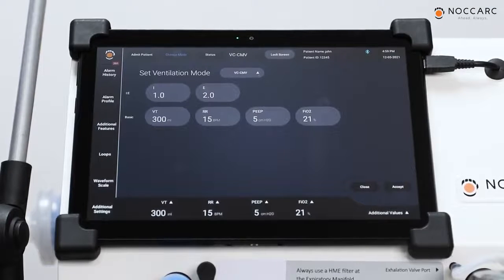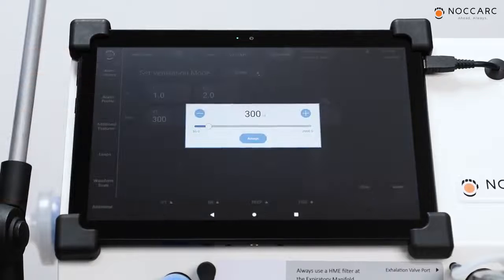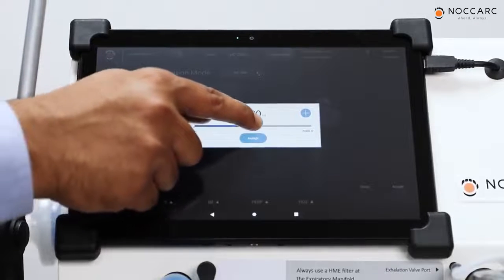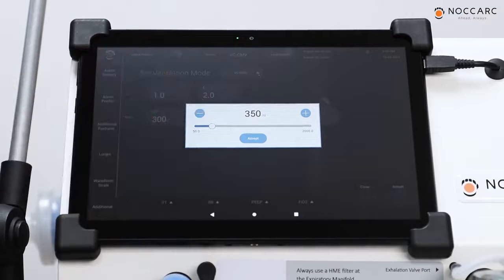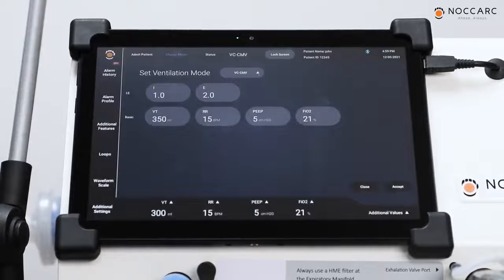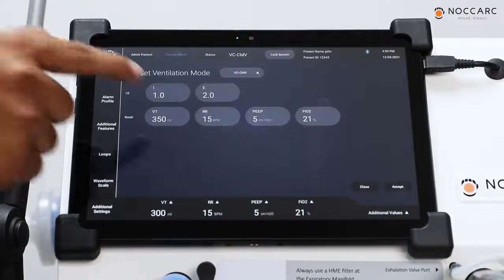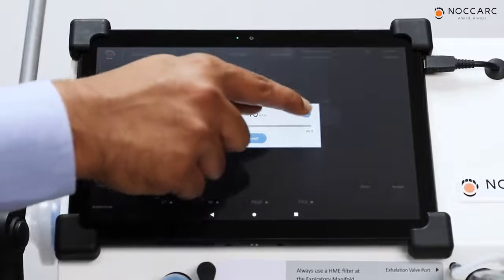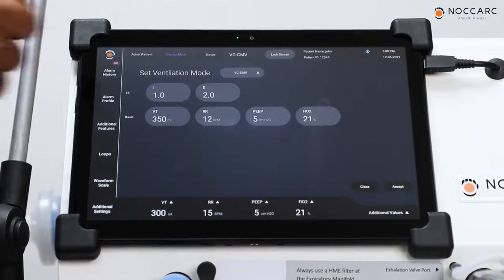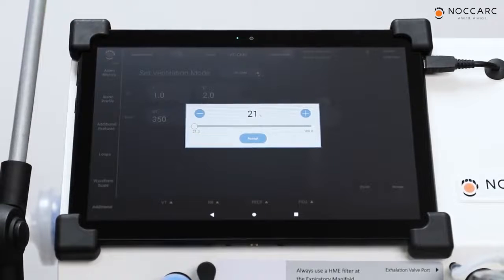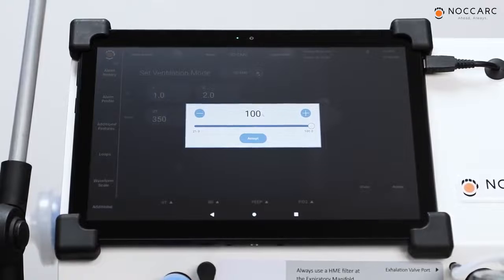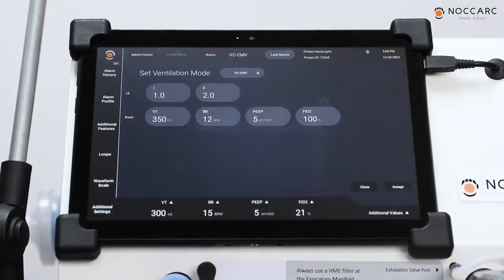To change any parameter, press on that particular parameter. Let's say I want to change the tidal volume. I will press on this VT. Now you can change the parameter by using this slider or by using these buttons. Accept it. Similarly, you can change other parameters. To set FiO2, press on FiO2. If you directly want to set FiO2 at 100%, take this slider directly to 100% and accept it. Once all parameters have been set, press on accept.